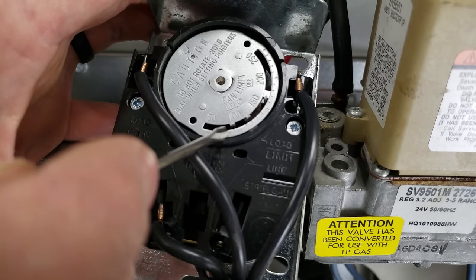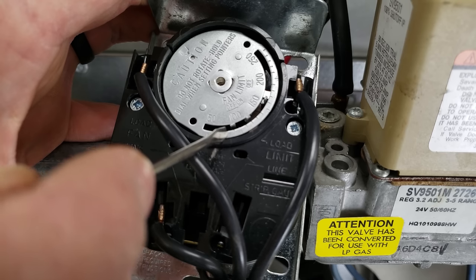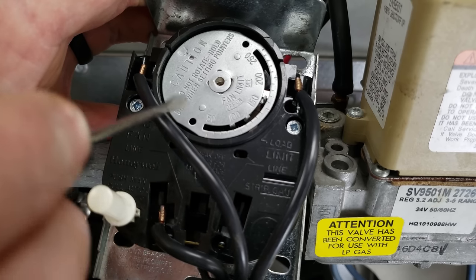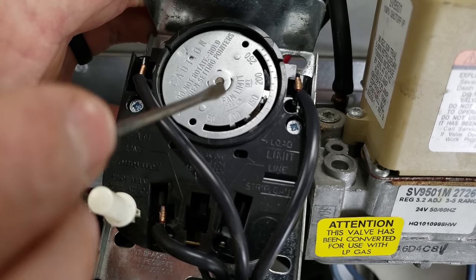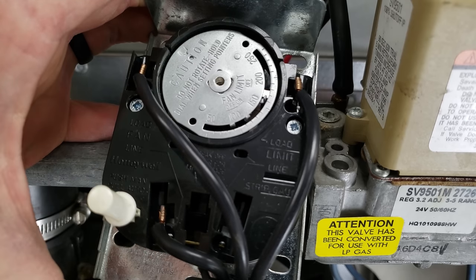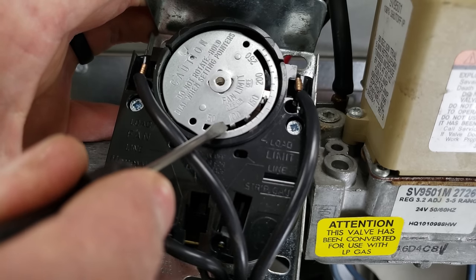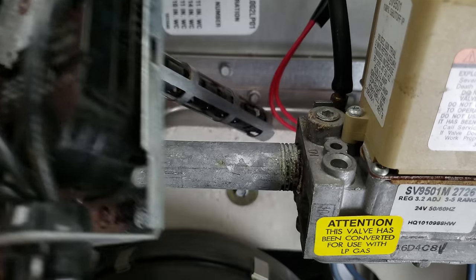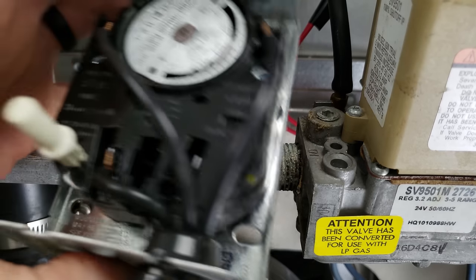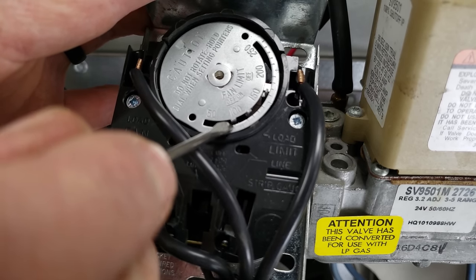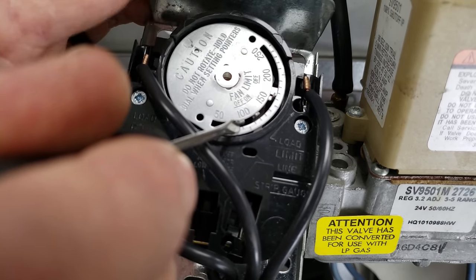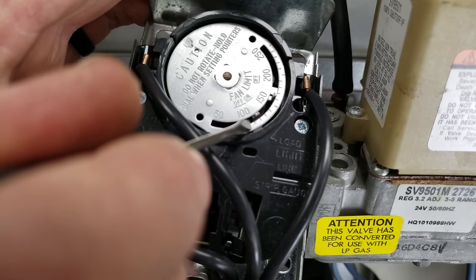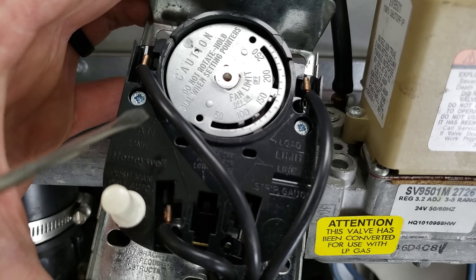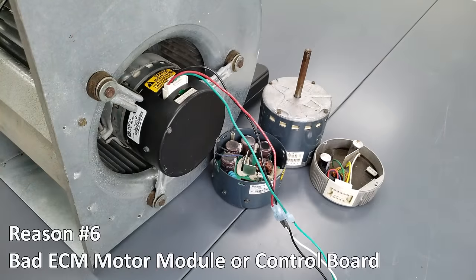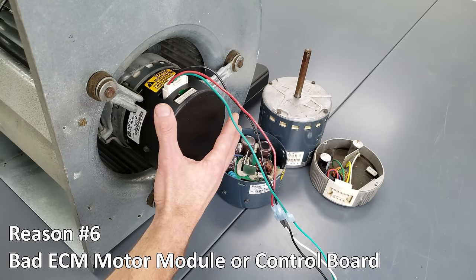If this is set down near 70 degrees and it's 70 degrees in the house, then it's going to allow the blower motor to just continue to run. And so you want to have this set up at 90 degrees. If this is out of parameters a little bit, you could try to adjust this up just a little bit higher, maybe to say 95 degrees, but really you want to go ahead and replace the fan limit control.